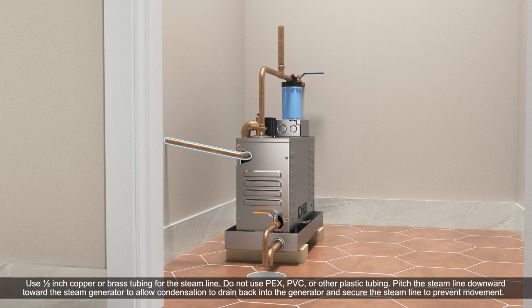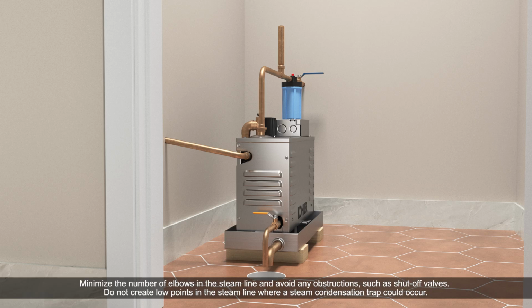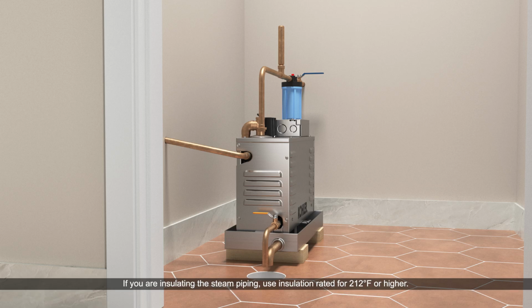Pitch the steam line downward toward the steam generator to allow condensation to drain back into the generator and secure the steam line to prevent movement. Minimize the number of elbows in the steam line and avoid any obstructions, such as shutoff valves. Do not create low points in the steam line where a steam condensation trap could occur. If you are insulating the steam piping, use insulation rated for 212 degrees Fahrenheit or higher.